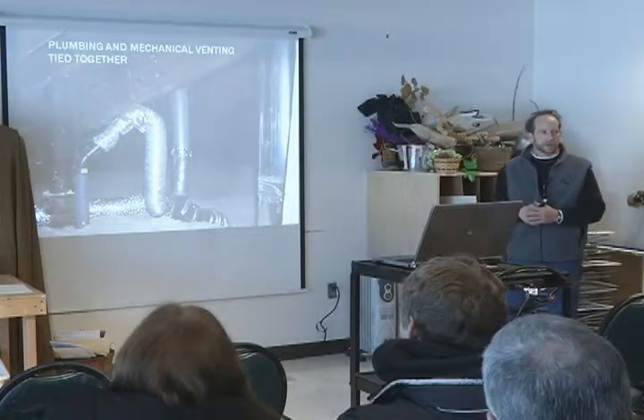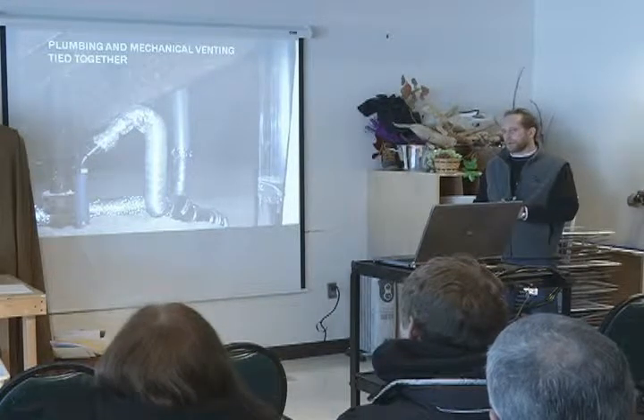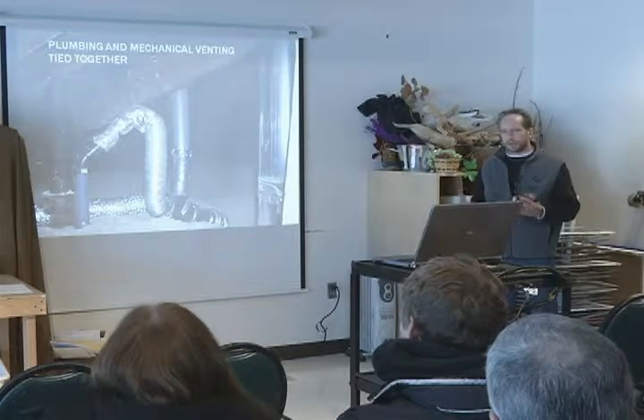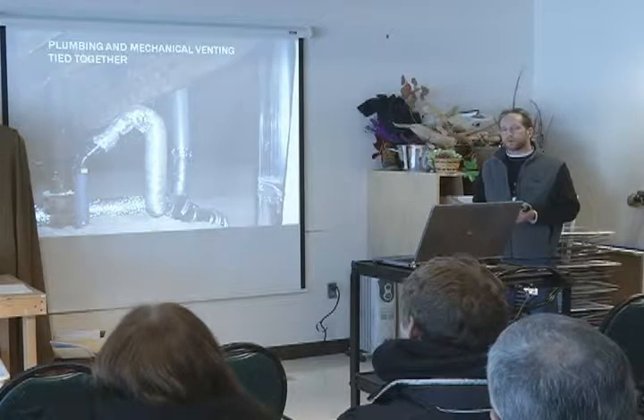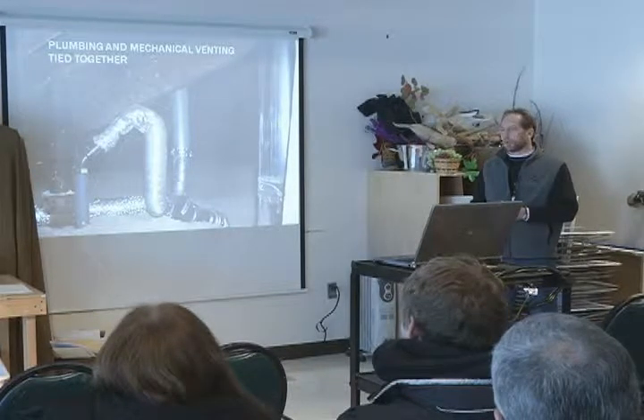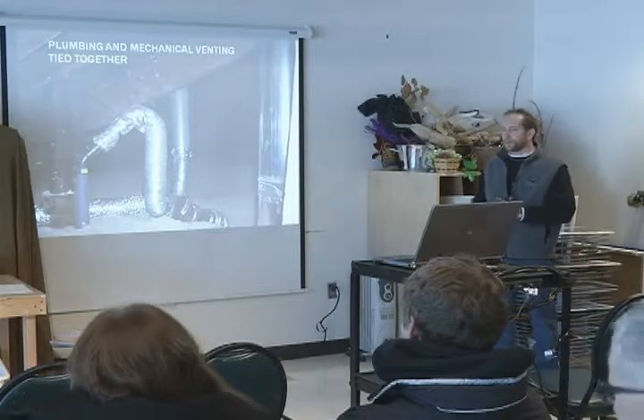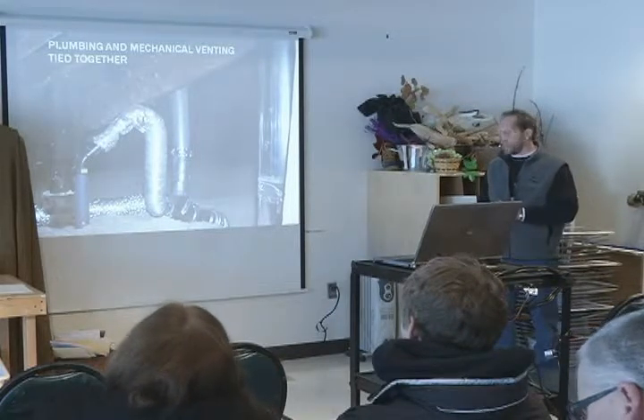Your plumbing venting is required to go through the roof. It is something we will make you correct and fix. Where you don't have venting, you're going to find a lot of clogs in your plumbing system. Your water's going to drain very slowly. It's more of a sanitary issue at this point.